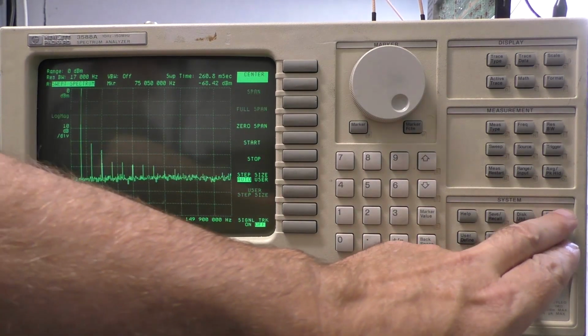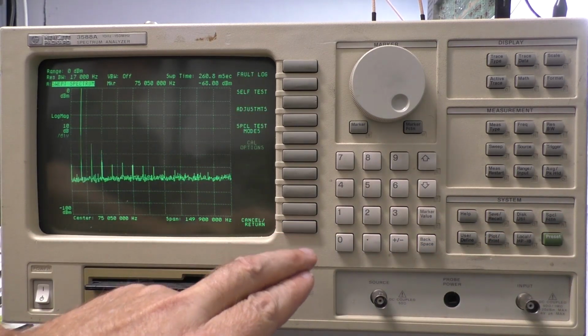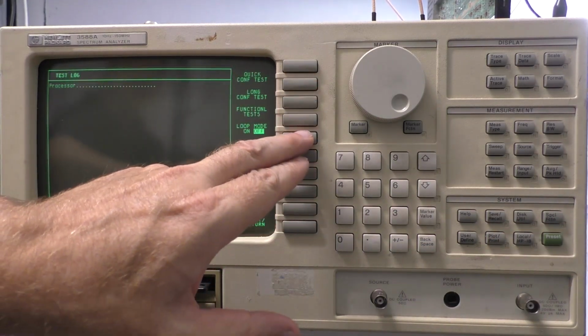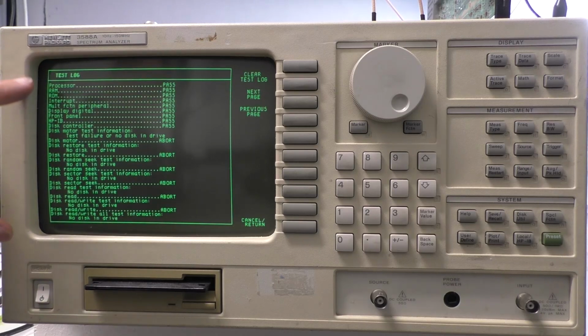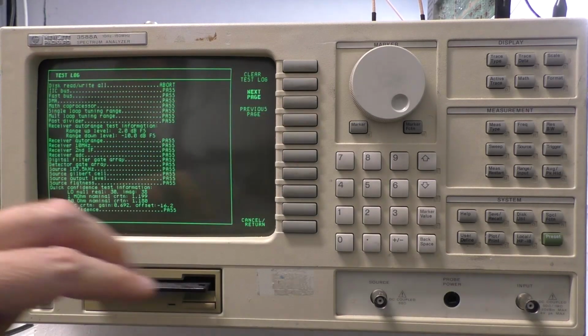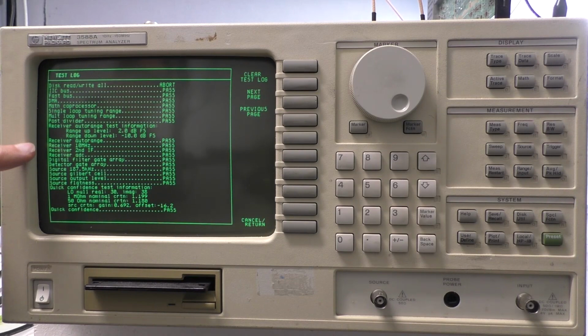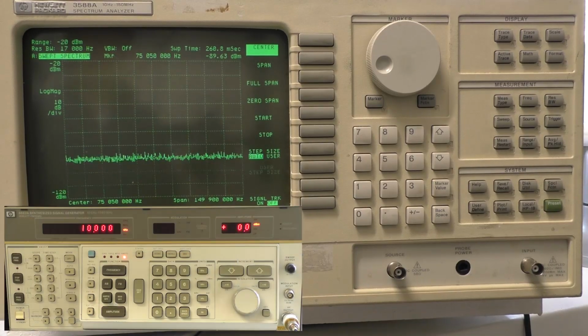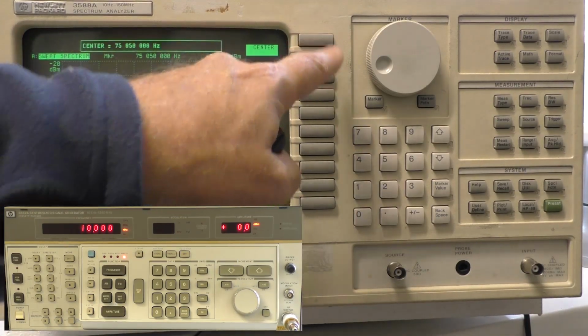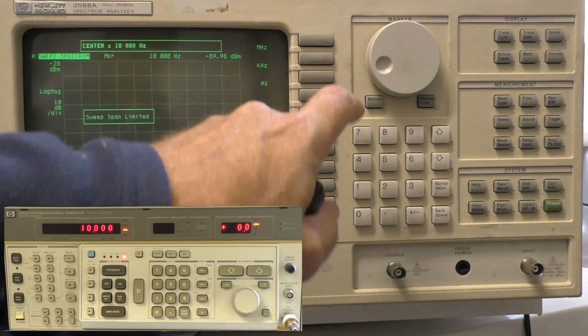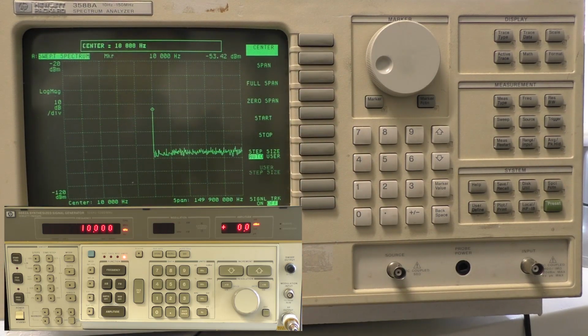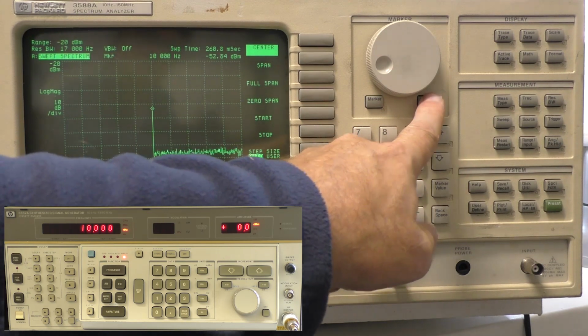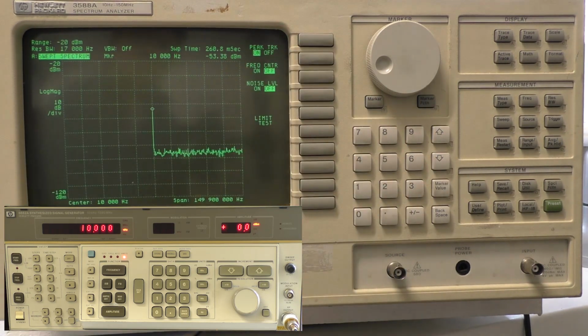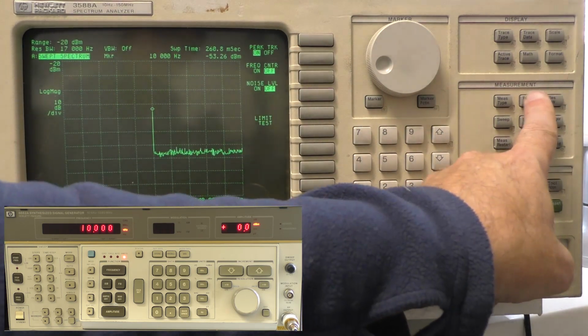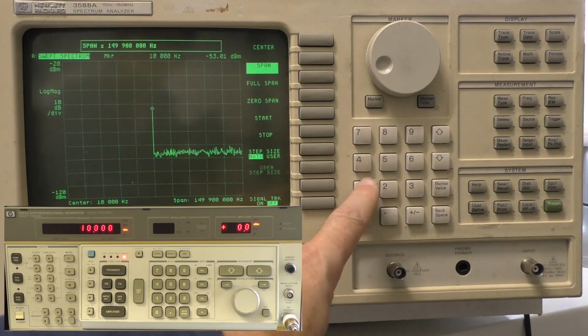Hit special function. Service functions. Self-test. Test log. Next page. All tests have now passed. Let's perform a few basic tests on the unit's attenuators. Set the center frequency to 10 kHz. This is to test the lower frequencies on the unit. Hit the marker function. Set peak tracking to on. Hit frequency. Span. Set to 100 kHz.